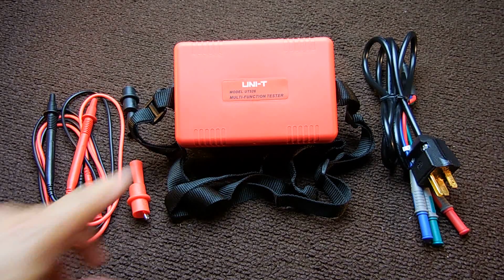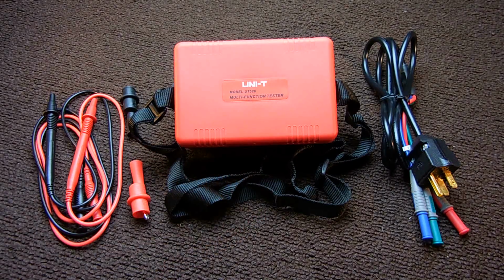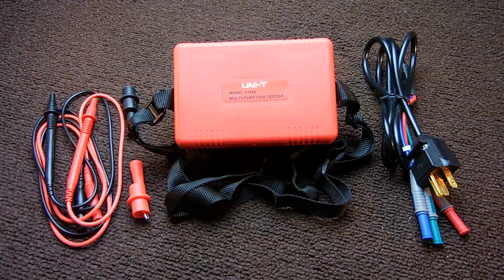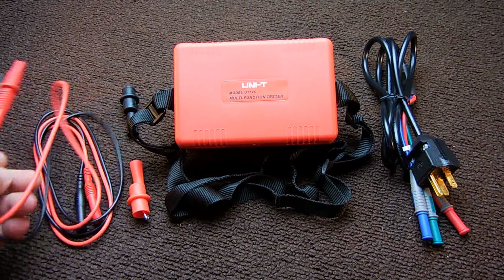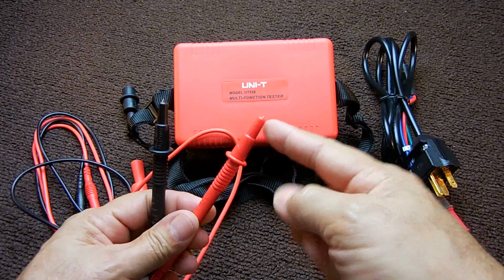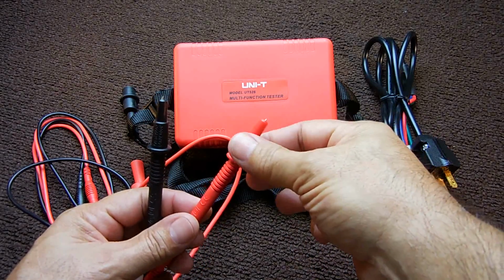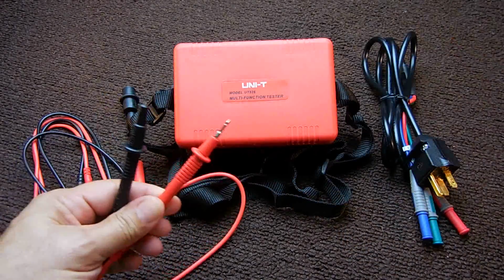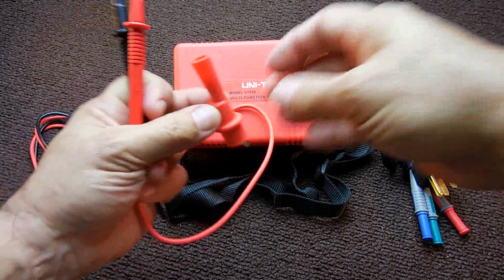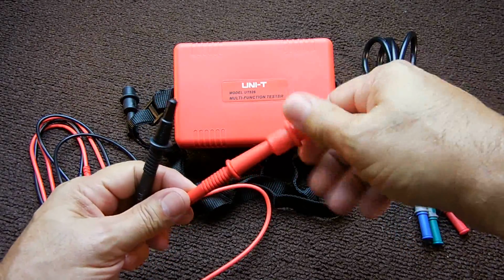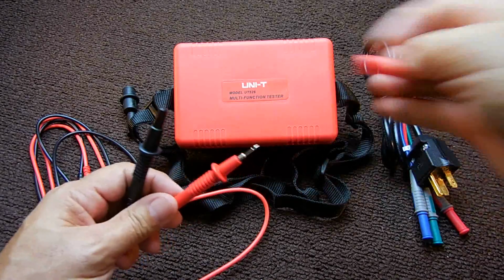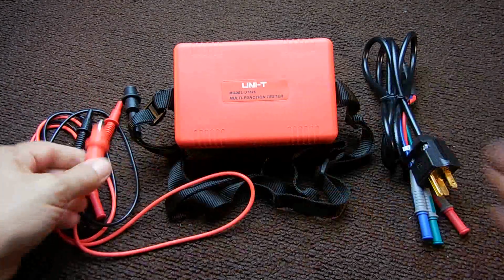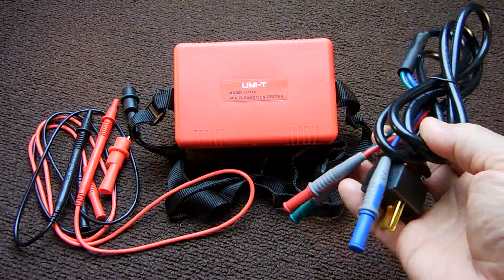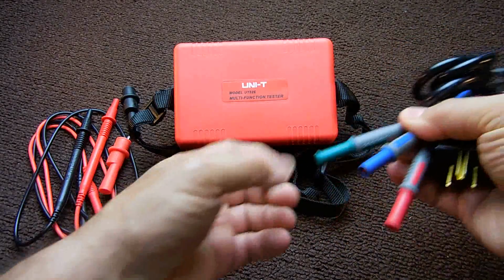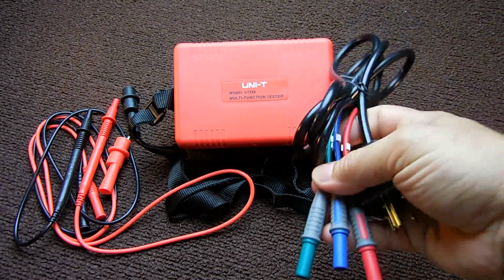Okay, you're now looking at the UNI-T Model UT526 Multifunction Insulation Tester. The unit is very compact, unlike the crank Megger. These are the probes. See, the tip is mostly covered to protect you from the high voltage during the test. These also pull off on both sides, and then you could take right here and screw these on. Alright. Put that back. Over here you have a special cord. This is an RCD cord. Remove these plugs, and I'll show you in a minute. This plugs into the unit for some testing.